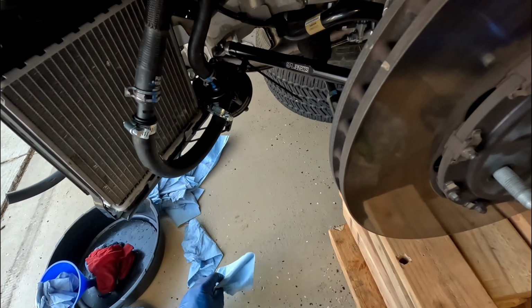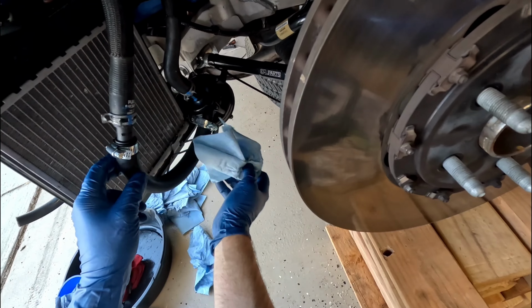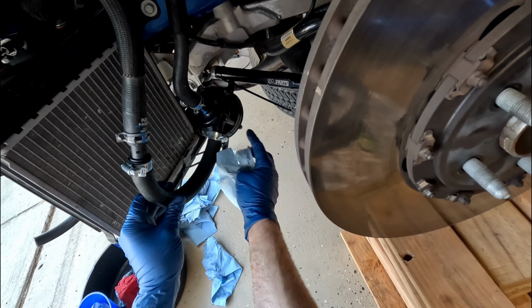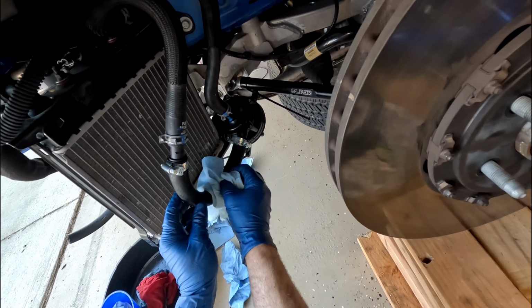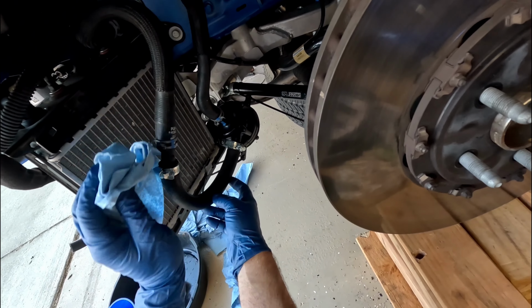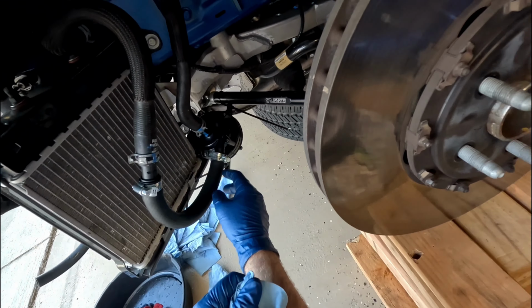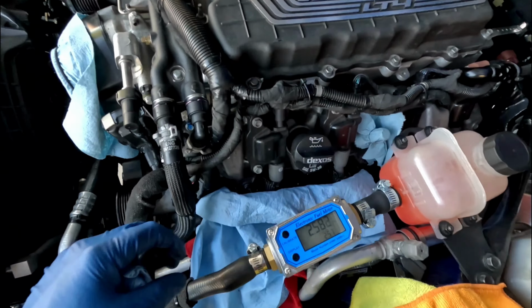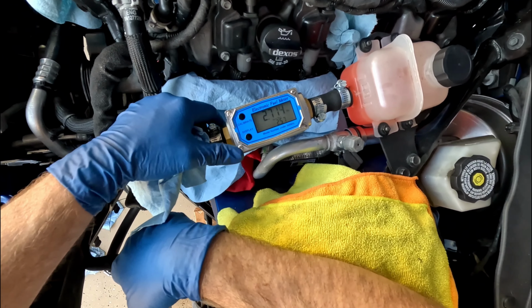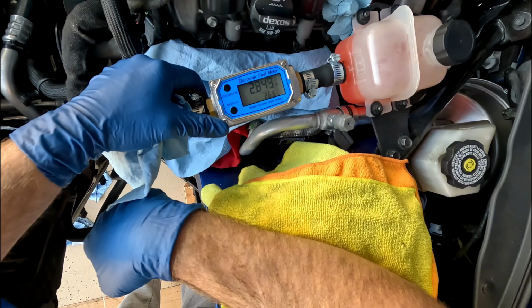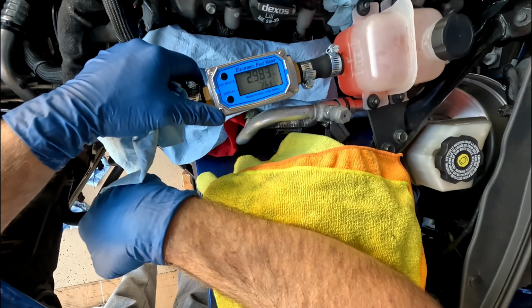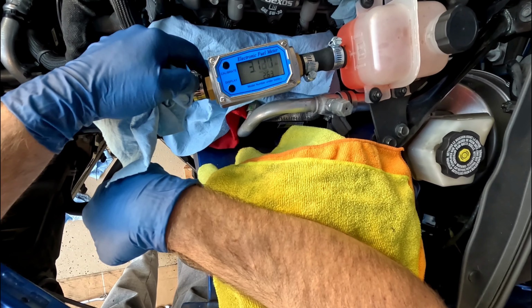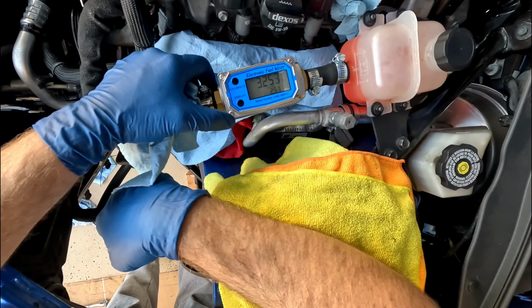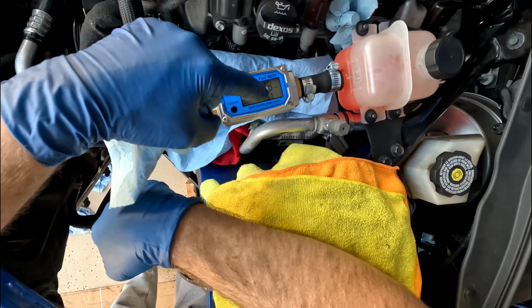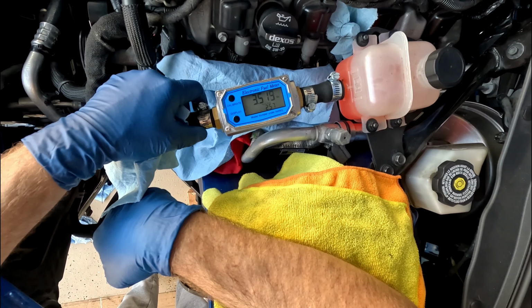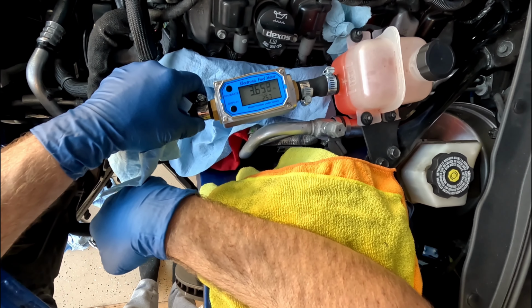Okay, so I basically hooked it all back the way I had it. Just running the whole system, going through both heat exchangers as well as the supercharger and the reservoir coming back to the pump. Now that I've changed the calibration factor, you can see it's showing a flow rate of 2.63, 2.57 gallons per minute. That was changing what I believe is known as the K factor, or just the conversion factor for how many times that turbine in there spins, how many gallons of fluid is actually going through it.